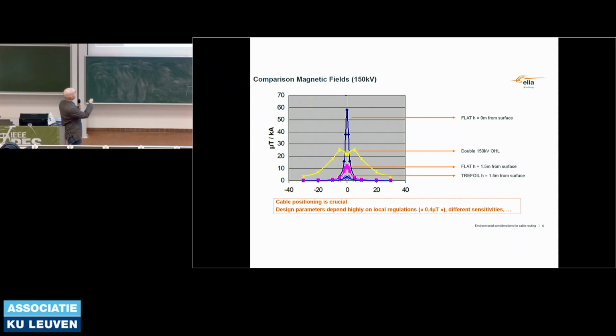Flat on the ground, immediately on the axis of the middle phase, you get the highest effect of the magnetic field. If you do the same but at 1.5 meters, about where humans and the human heart live, this will sag down to about 10 microtesla per kiloamp - scaled up or down with the current passing through. So the flat position comes here, and trefoil is about a fifth or sixth lower.